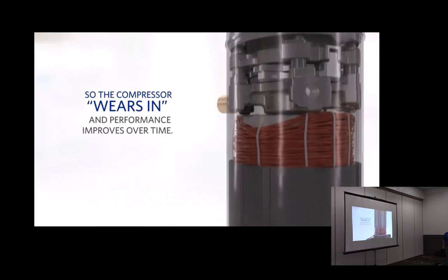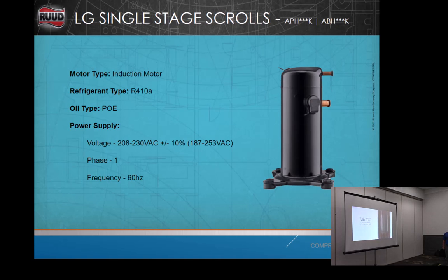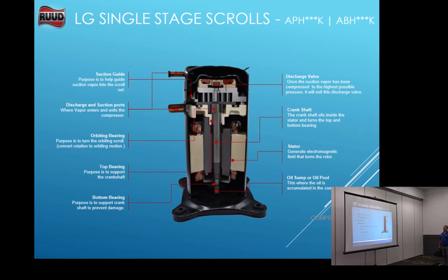Our LG single stage is pretty much the same. I mean, it's not a lot different. It's just made by LG. They have a suction guide, not a suction funnel per se, because the suction funnel for Copeland has gotten kind of a bad name. Theirs is metal, where the Copeland is plastic, but there's never been any issues with the plastic part coming apart. It's been the scroll plates inside that break, okay? So not really any different. There are some people I've heard out there that sell Carrier. It's all the same compressor. You can ask Copeland. They don't make special compressors for Daikin or anybody else or Carrier.